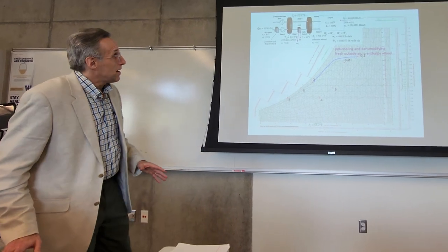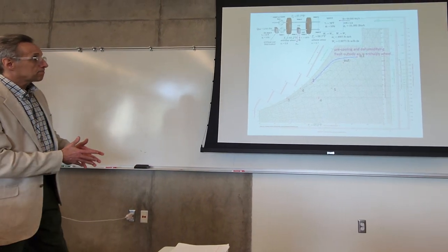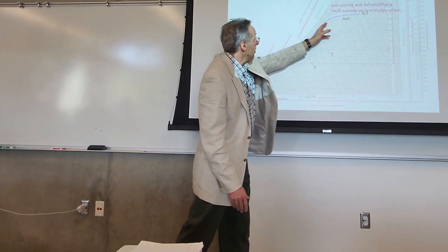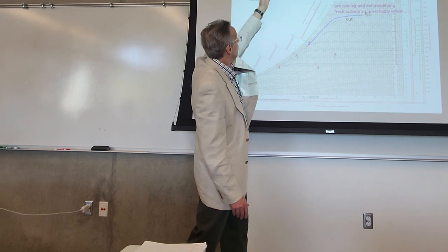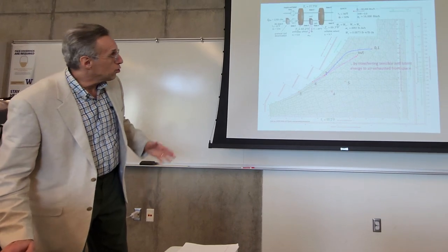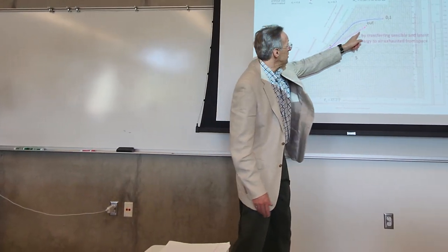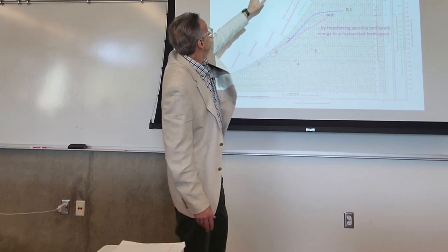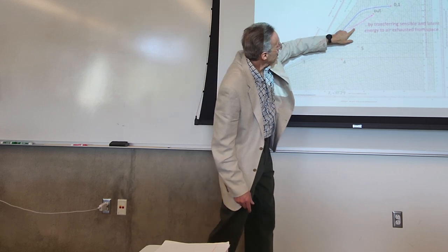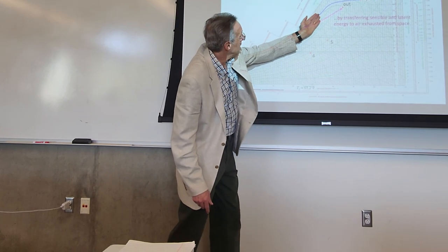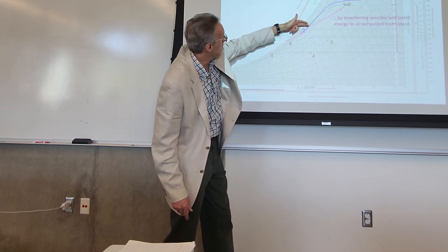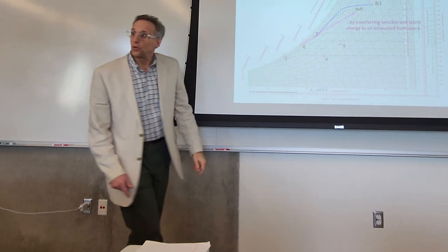We can see that we're coming in and bringing in outside air at 0. And then we're cooling it as it flows through the enthalpy wheel, and it's being cooled by this air that's passing by. So this air from 6 to 7 is leaving. You see this air is nice and cool, and it's heading out, and it's absorbing latent and sensible energy from that outside air and bringing it down to 2.